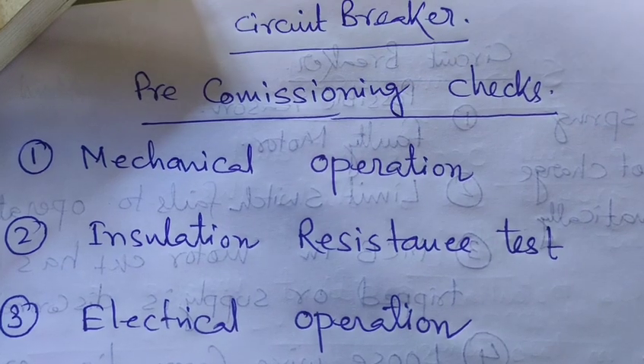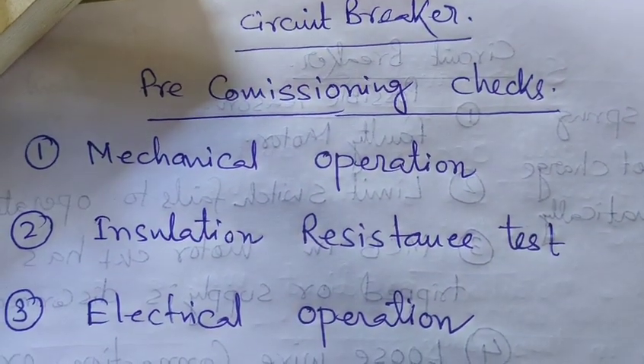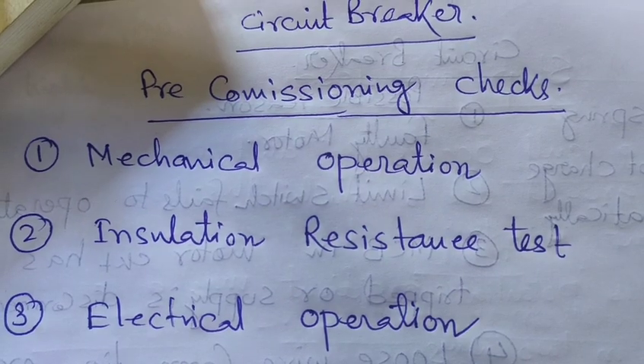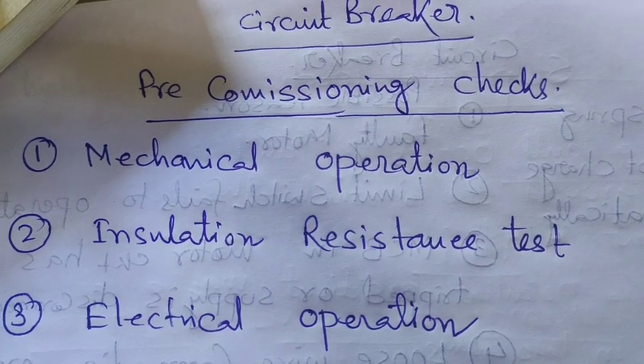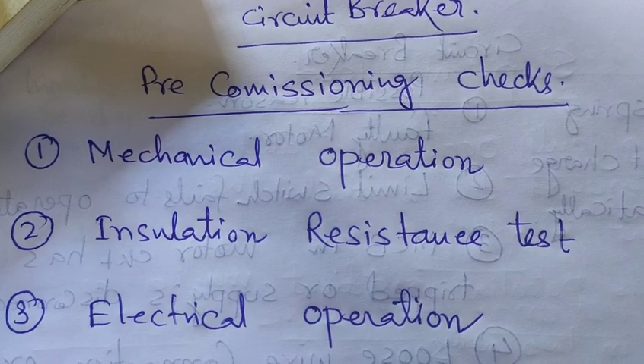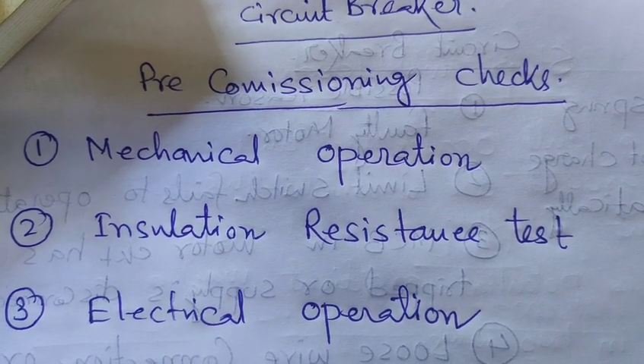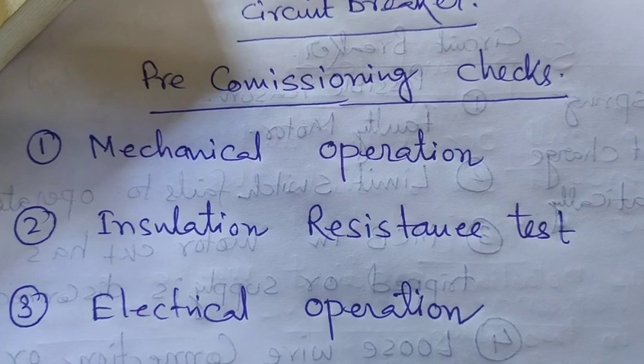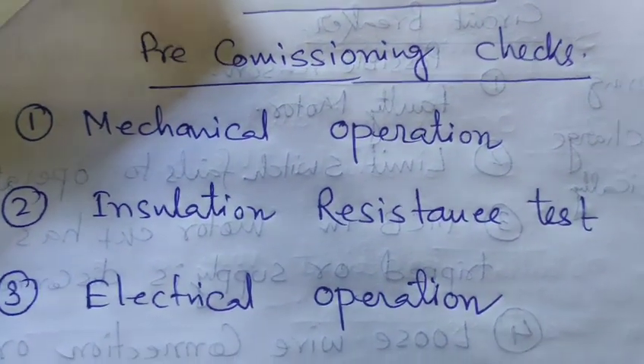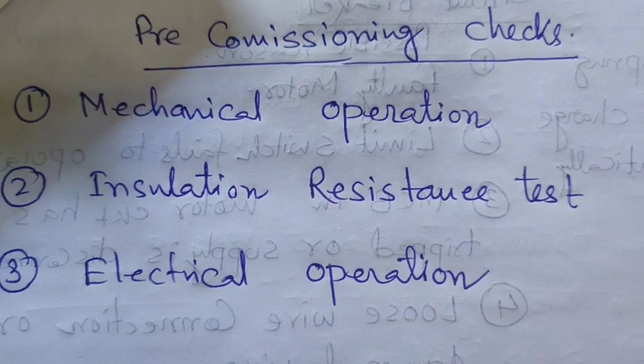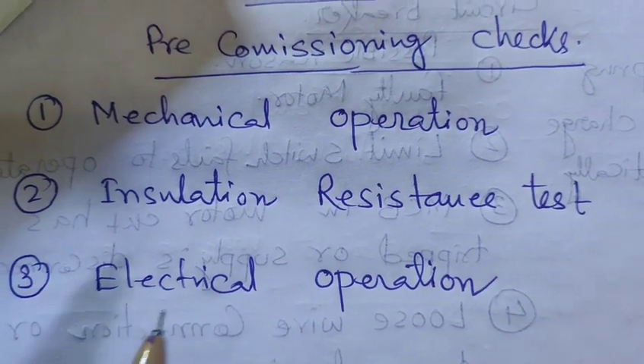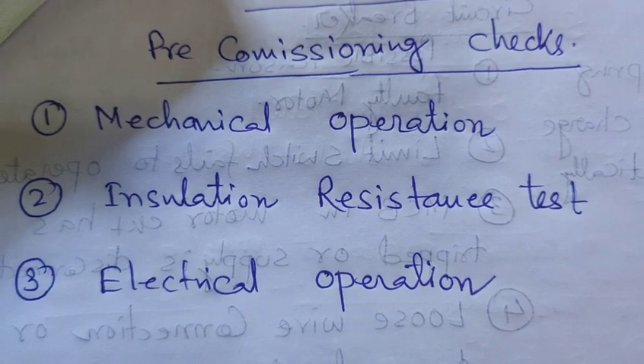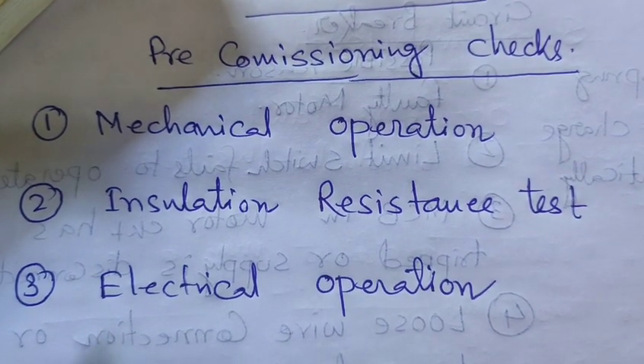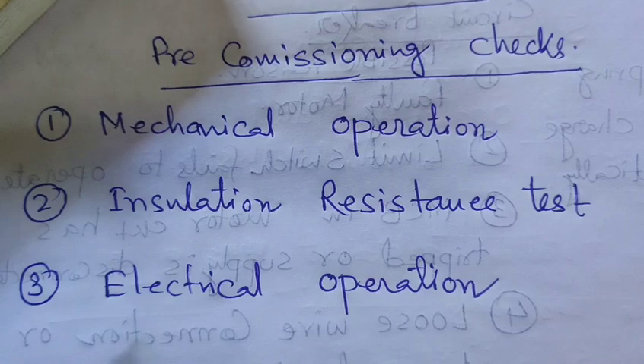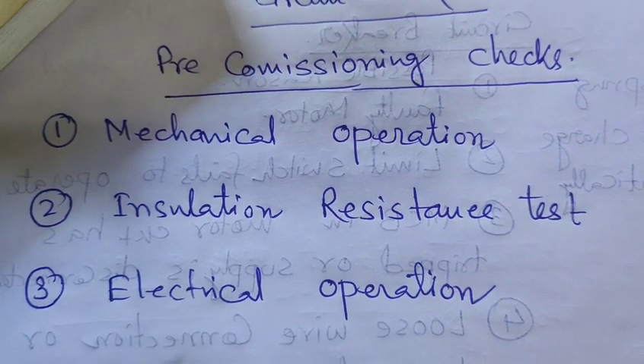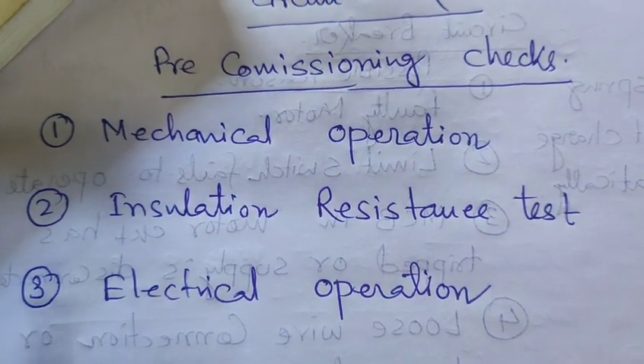Today our discussion topic is circuit breaker pre-commissioning check: how you have to check your circuit breaker before commissioning. There are three types of checking. First is the mechanical operation check, second is the insulation resistance test, and third is the electrical operation. Today I am discussing the 33 kV VCB vacuum circuit breaker pre-commissioning check method.